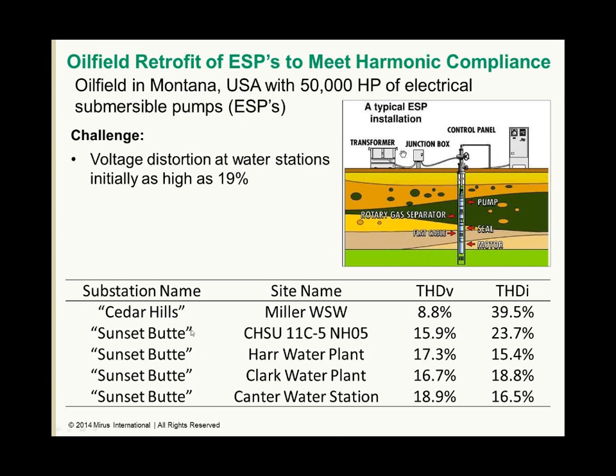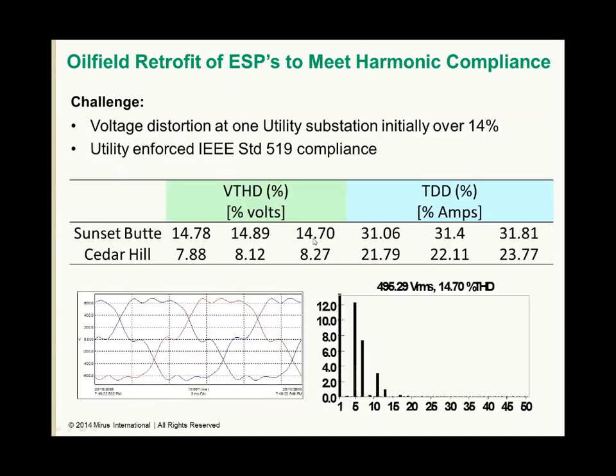So these were the ESP pumping water stations, where the electrical distribution was, and we can see we've got almost 19% voltage distortion at this Cantor water station. At one of the utility substations supplying the oil field, voltage distortion was over 14%. This was well above IEEE Standard 519 requirements and was causing problems with neighboring customers. So the utility enforced the standard's harmonic limits on the oil company. Although there were a lot of VFDs at the site, the voltage distortion level still seemed excessive to me. And when the voltage waveform was observed, the oscillations at the peak again seemed to indicate power system resonance.